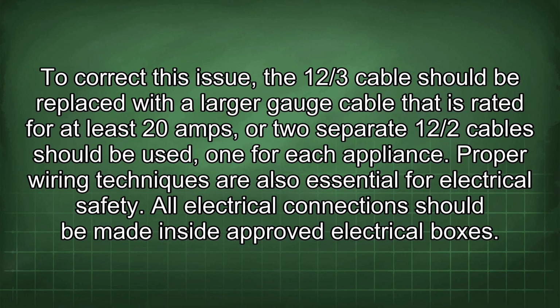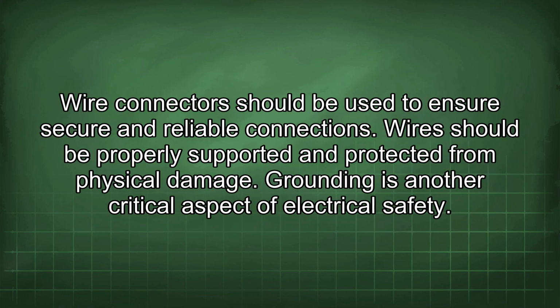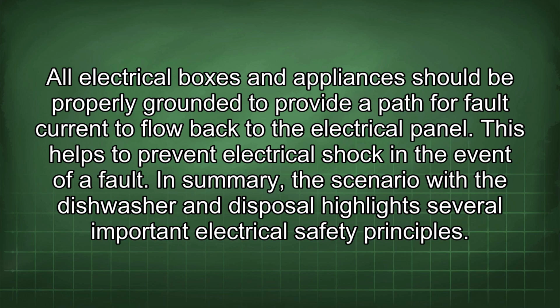Proper wiring techniques are also essential for electrical safety. All electrical connections should be made inside approved electrical boxes. Wire connectors should be used to ensure secure and reliable connections. Wires should be properly supported and protected from physical damage. Grounding is another critical aspect of electrical safety. All electrical boxes and appliances should be properly grounded to provide a path for fault current to flow back to the electrical panel. This helps to prevent electrical shock in the event of a fault.